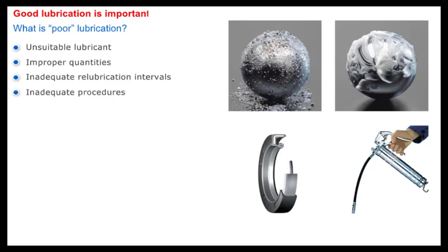Moreover, bear in mind that often, once the bearing has been properly installed and sealed, the only contact that it will have with the exterior will be by means of any lubricant that may be added from time to time. Therefore, providing clean and cool lubricant is another key element of a maintenance program if the lifespan of a machine component is to be maximized.